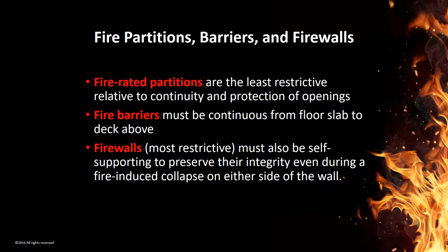Some more on the IBC terminology on fire resistance rated walls. One type is called a fire rated partition. The partition is the IBC terminology and it is the least restrictive relative to IBC code requirements for continuity and protection of openings in the wall. Specifically in terms of continuity, a partition may stop at a ceiling — it doesn't have to go slab to slab to the deck above. A fire barrier does; it's the next higher level of requirements and must be continuous from the floor slab below to the deck above, going through a ceiling and being complete all the way top to bottom.